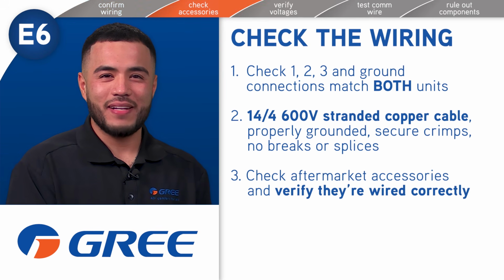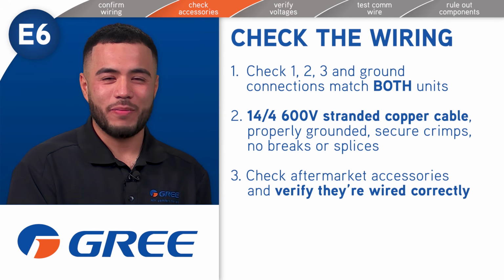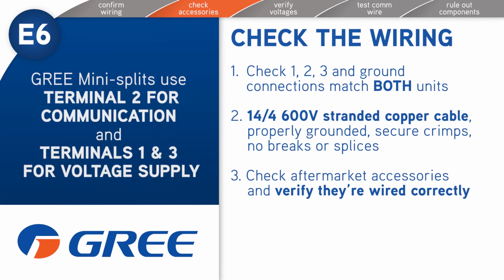Next, if a condensate pump, float switch, or disconnect is installed, verify they are wired correctly. Aftermarket accessories can interrupt communication if miswired. As a reminder, GREE branded mini splits use terminal 2 for communications and 1 and 3 for voltage supply.